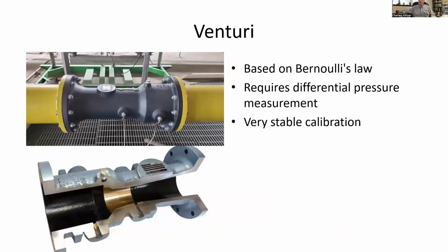Now, the last one is actually my favorite, and it's my favorite because that's what we use in our testing laboratory. That picture you see there with a dark colored device with a yellow pipe, that's actually the picture of the meter that we use in our testing laboratory. It's one of several, and it's a particular type called the Venturi meter. Down here at the bottom, you see is a cutaway of that exact same type of meter. And these meters are nice, and we like them at CIT's laboratory for one simple reason. Their calibration lasts a very, very long time. In fact, the meter that we have installed here, its calibration is guaranteed for the lifetime of the meter. We never have to get it recalibrated.